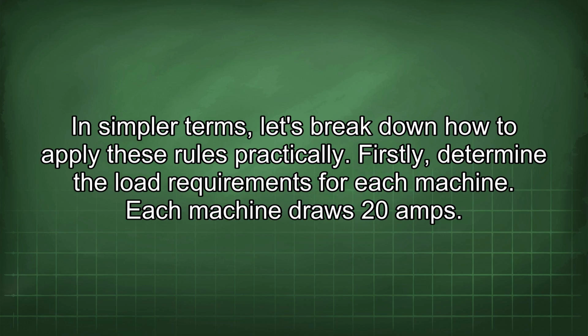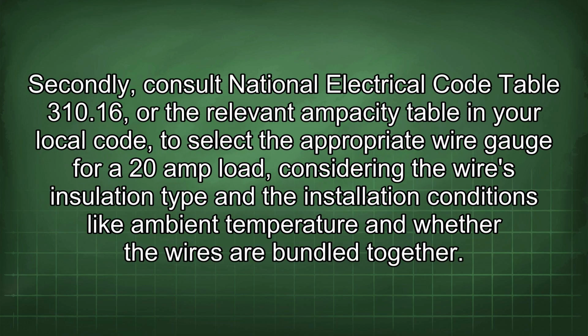Firstly, determine the load requirements for each machine. Each machine draws 20 amps. Secondly, consult National Electrical Code Table 310.16 or the relevant ampacity table in your local code to select the appropriate wire gauge for a 20 amp load, considering the wire's insulation type and the installation conditions like ambient temperature and whether the wires are bundled together.